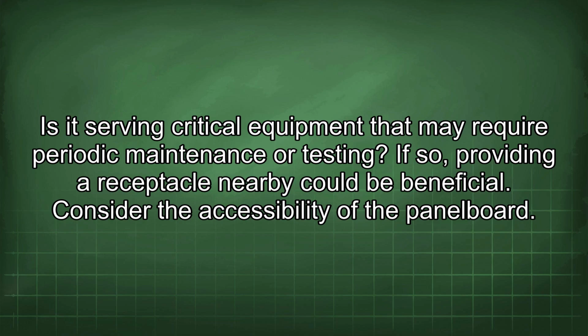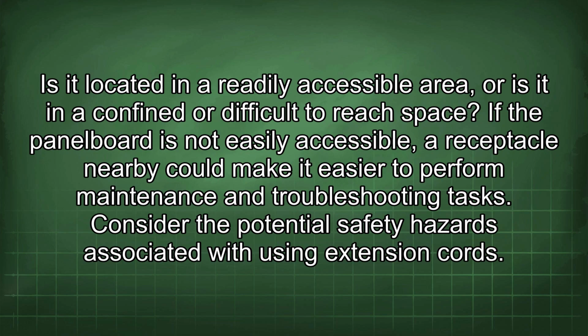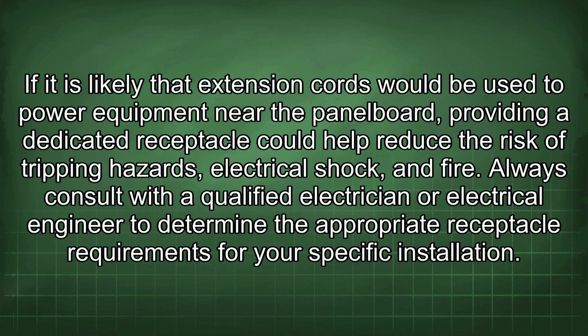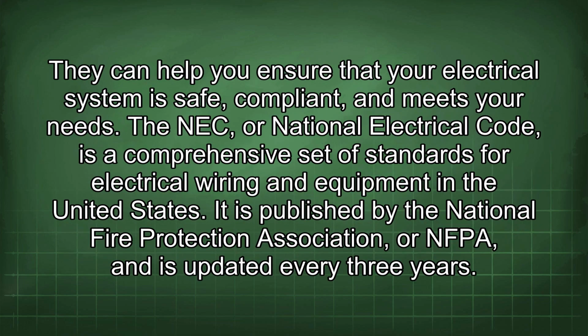Consider the accessibility of the panel board. Is it located in a readily accessible area, or is it in a confined or difficult to reach space? If the panel board is not easily accessible, a receptacle nearby could make it easier to perform maintenance and troubleshooting tasks. Consider the potential safety hazards associated with using extension cords. If it is likely that extension cords would be used to power equipment near the panel board, providing a dedicated receptacle could help reduce the risk of tripping hazards, electrical shock, and fire. Always consult with a qualified electrician or electrical engineer to determine the appropriate receptacle requirements for your specific installation. They can help you ensure that your electrical system is safe, compliant, and meets your needs.